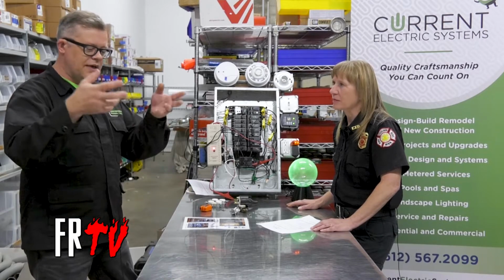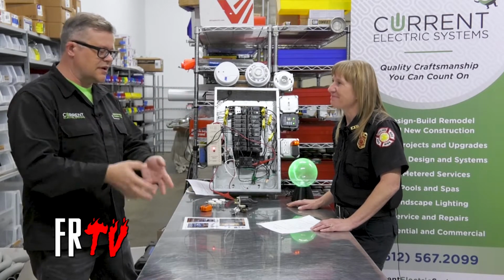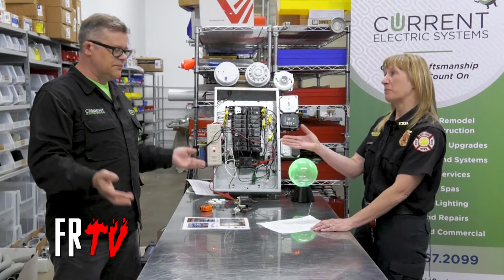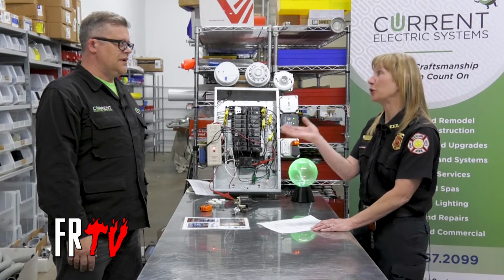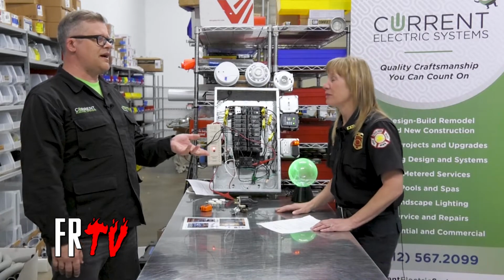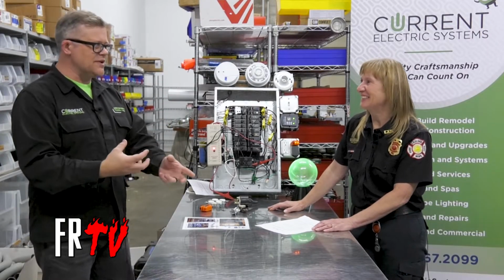And then past that, you have non-metallic methods, you have flex and conductors, and a lot of these are still in play today. There's just a difference between whether the equipment ground is present or not. And this is something an electrician like you needs to look at. Yes, so this is why we get this call a lot, like, well, I opened up the receptacle and I saw it and I just replaced it like I saw it, like it was there, which is great if what was there was right. If it's not, and you're just copying what's there, you're just perpetuating a problem potentially.